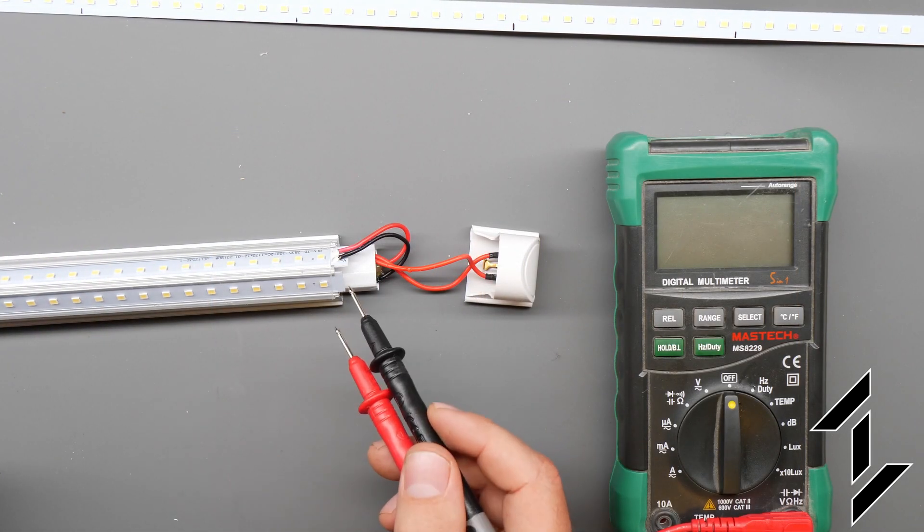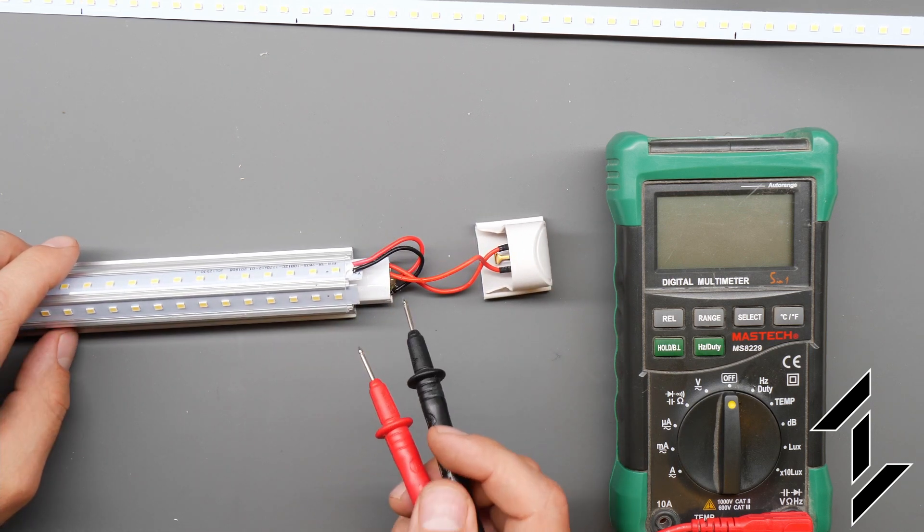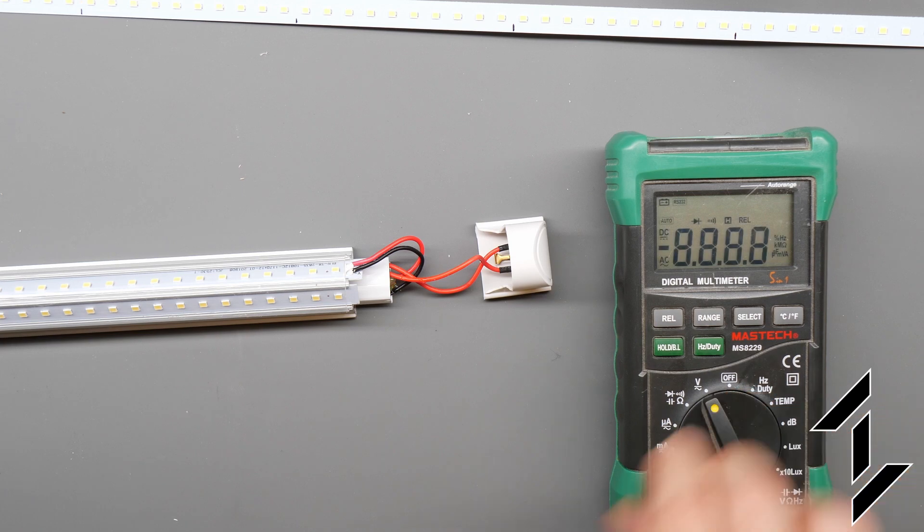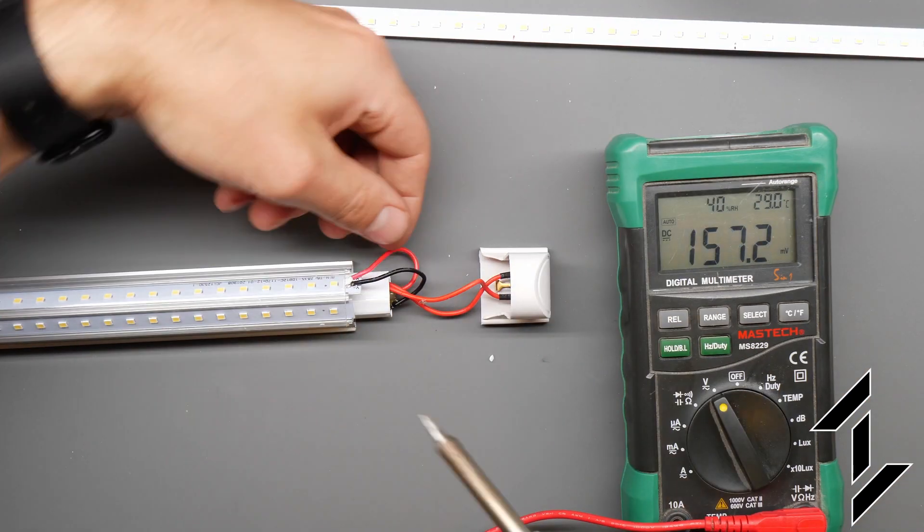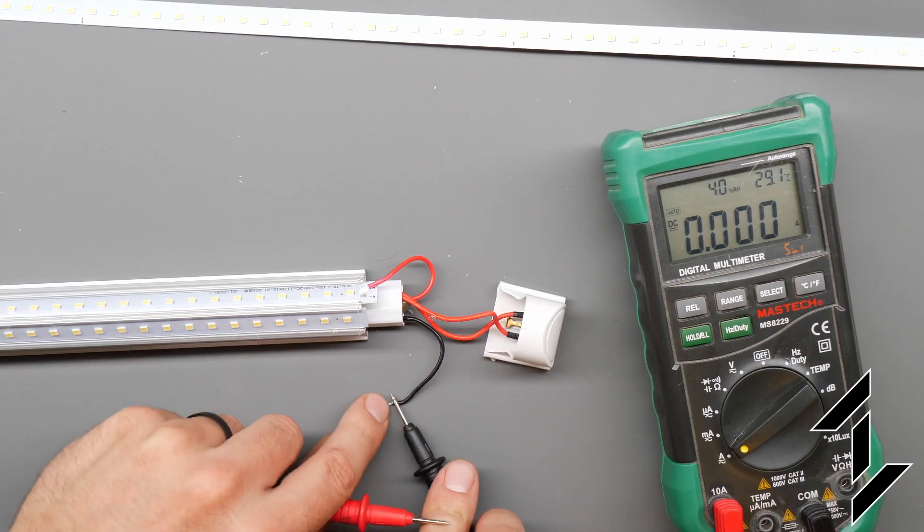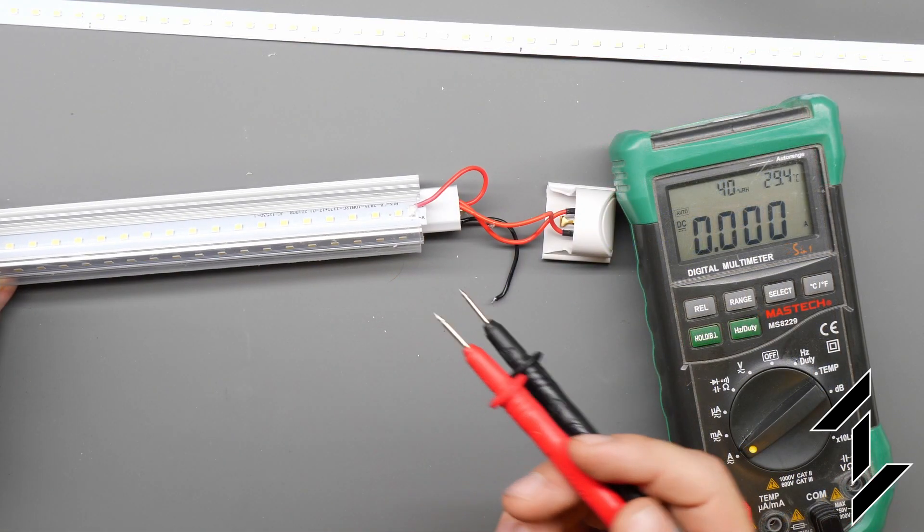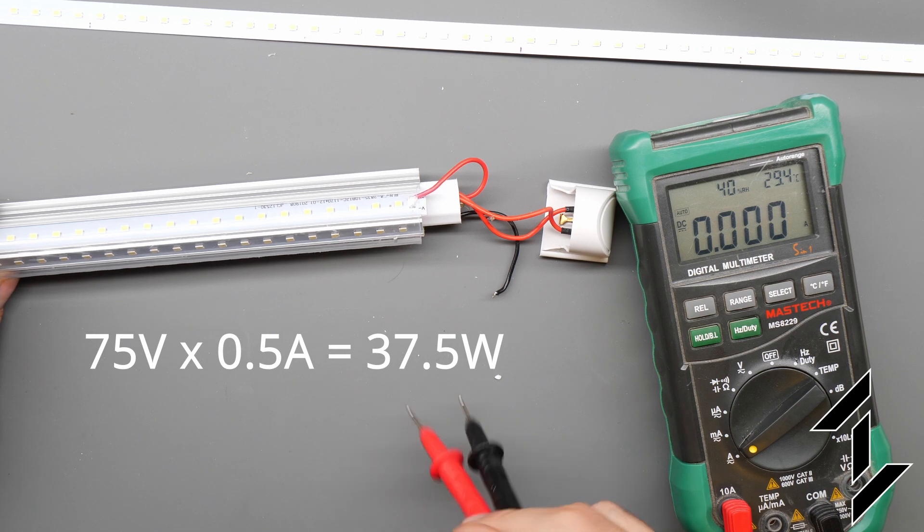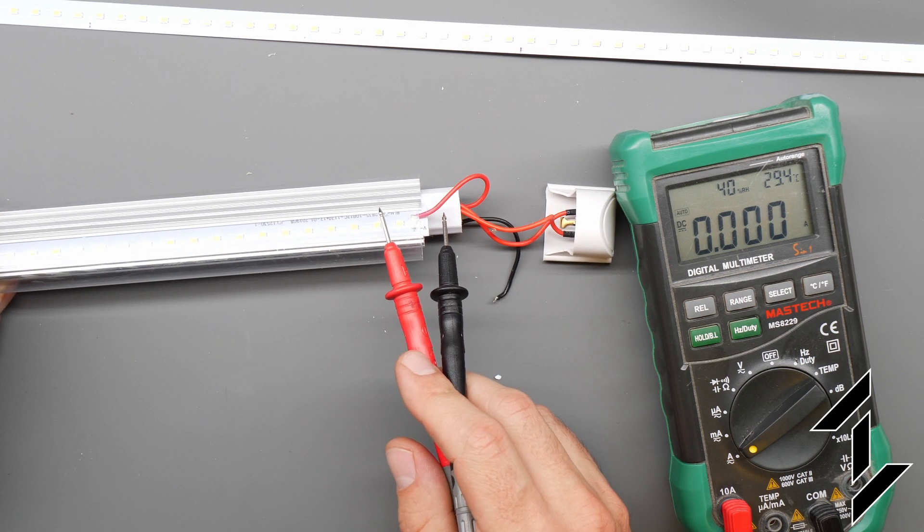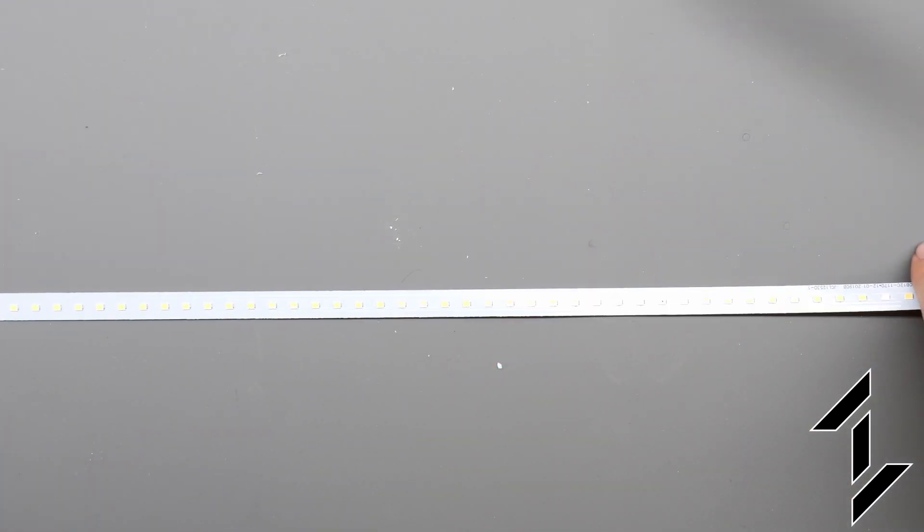Now before we test our hypothesis on why these are failing we're going to take a working strip and get the voltage and current off of that just so we have working condition values. So for voltage it looks like we're around 75 volts. And it looks like we're pulling just about half an amp. Now doing some quick math 75 volts times half an amp is 37.5 watts. Now these are supposed to be 40 watt fixtures so we're in the ballpark of what we expect.